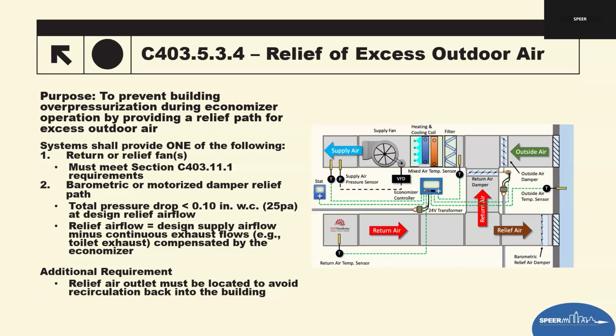And then the required relief airflow must equal design supply airflow minus continuous exhaust rates, especially exhaust fans like restrooms, for those makeup airs supplied by the economizer. So locating the relief outlet, the relief outlets must be placed so that the discharge air does not recirculate back into the building, kind of like in residential when you have mechanical ventilation. So this is a common design mistake. So if the relief air gets back into the outdoor intake, then the system becomes unstable and wastes energy.